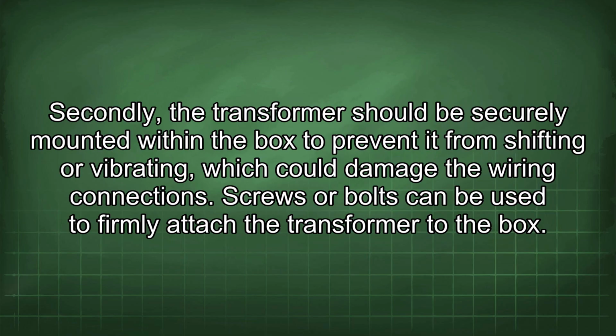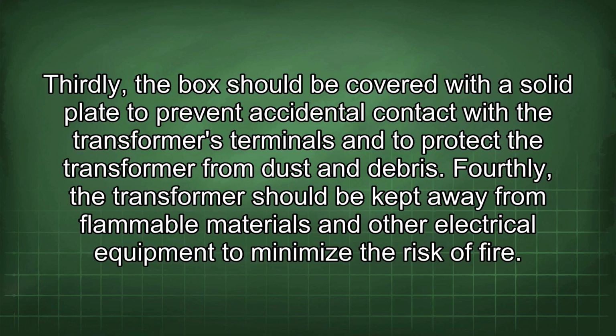Secondly, the transformer should be securely mounted within the box to prevent it from shifting or vibrating, which could damage the wiring connections. Screws or bolts can be used to firmly attach the transformer to the box. Thirdly, the box should be covered with a solid plate to prevent accidental contact with the transformer's terminals and to protect the transformer from dust and debris.